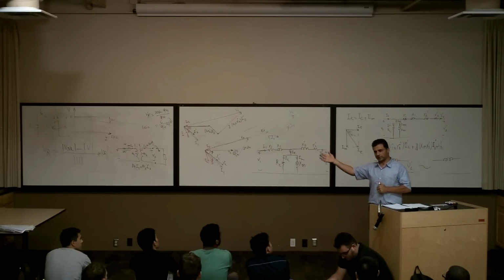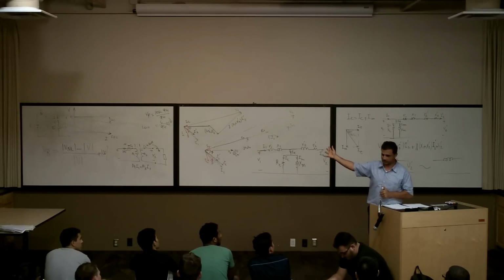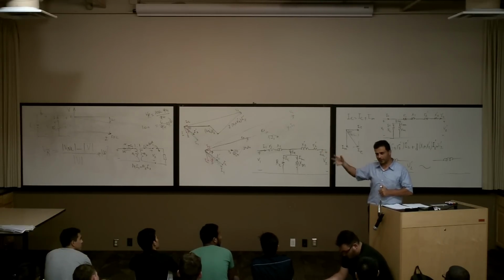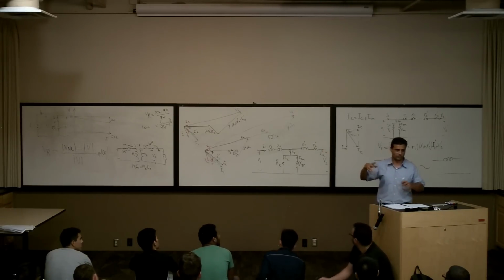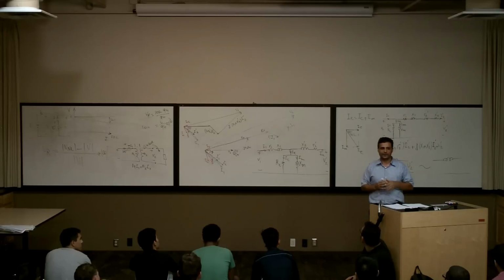Now, we redesigned the thing. I did the calculation. I'm not a power system engineer, but I know these things well. These are basic for power systems. I did the calculation for them. I'll bring one slide to show you a real system, how they show them and how they calculate. Because when you are going to put the inductor in this system, you have to calculate lots of things. It should be able to hold on to the short circuit current. It should be able to handle the nominal current, those kinds of things.